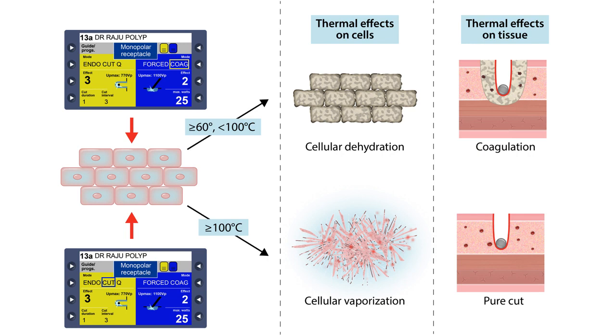So this is how a cut current and a coagulation current create their effect: by vaporization and coagulation by dehydration and coagulation of the proteins.